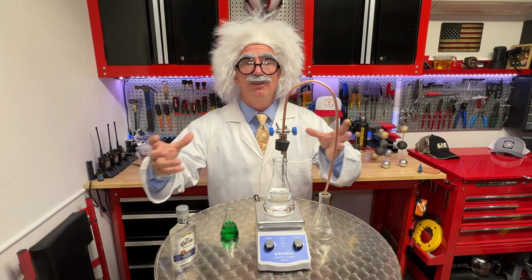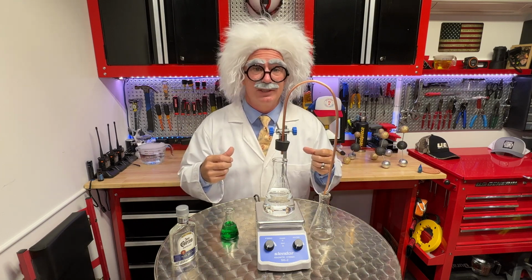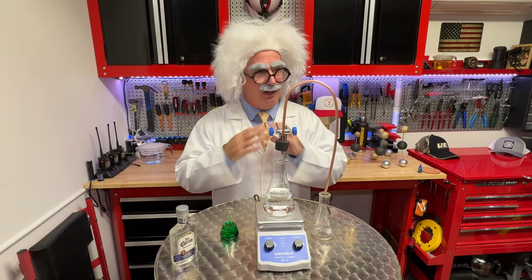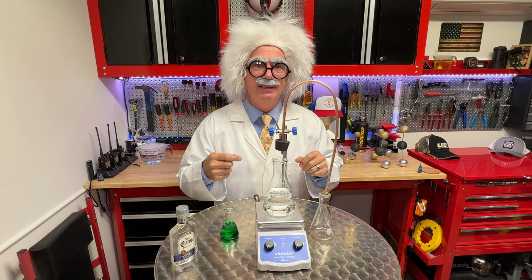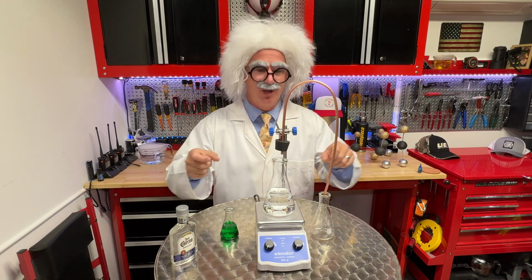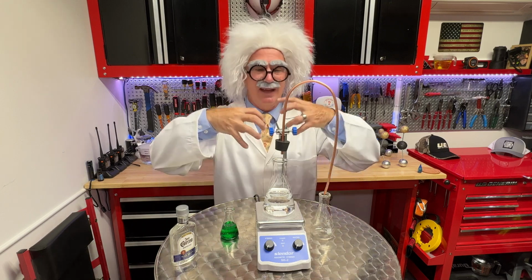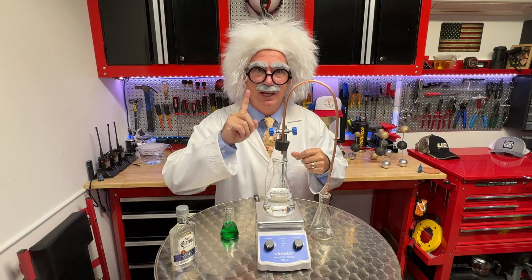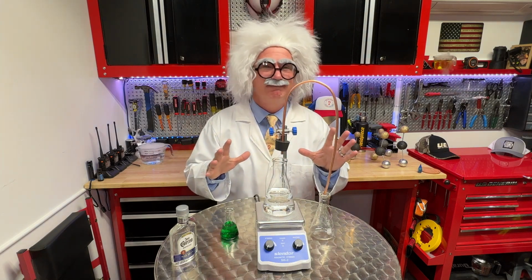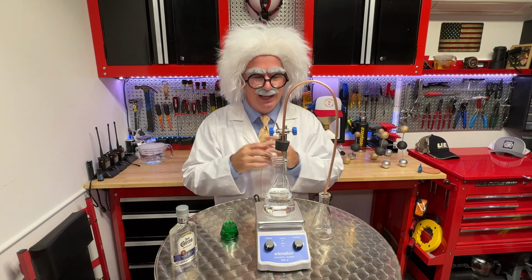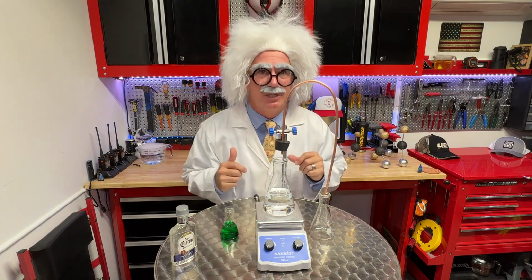I can take two different chemicals with two different boiling points, mix them together, and they are happy as can be. And so when we look at our PT chart, there's only one number that we reference because those two different boiling points have now come together and have a new common boiling point. But our 400 series refrigerants, it's not really like that, right? So let's do a little experiment.